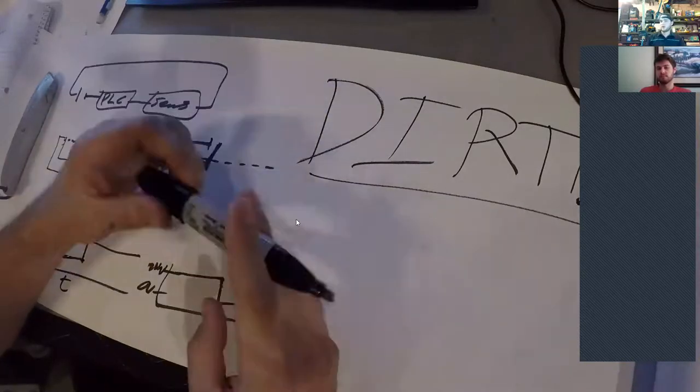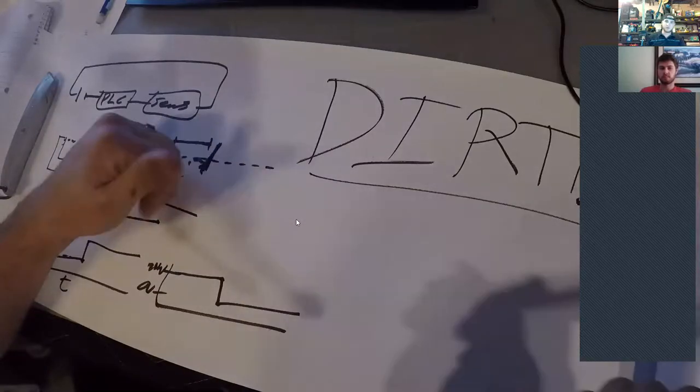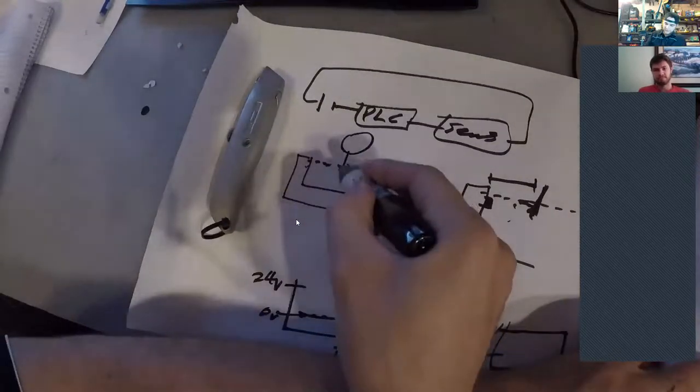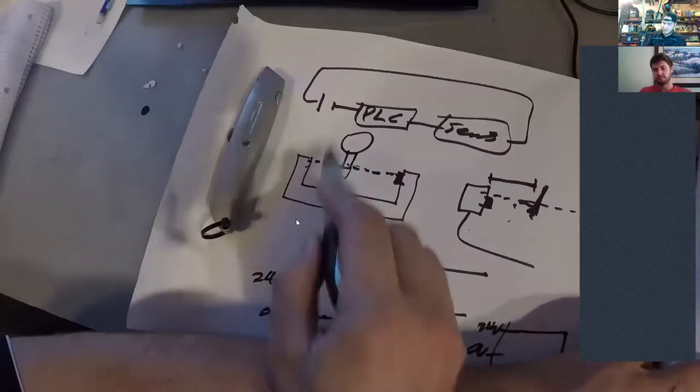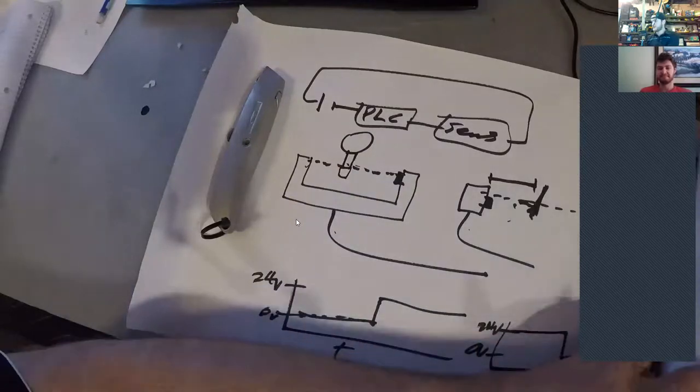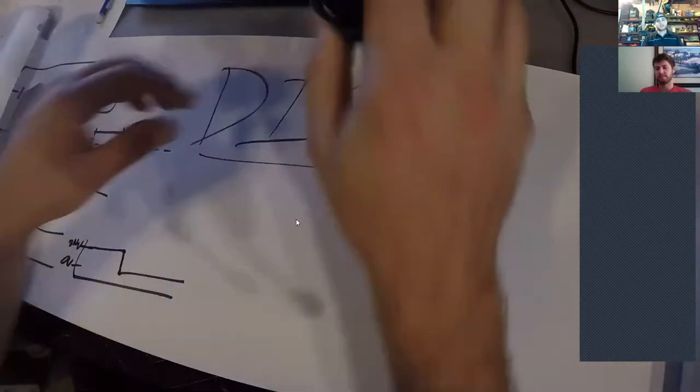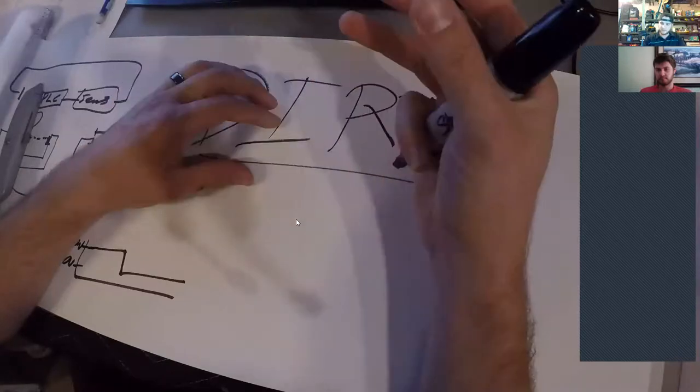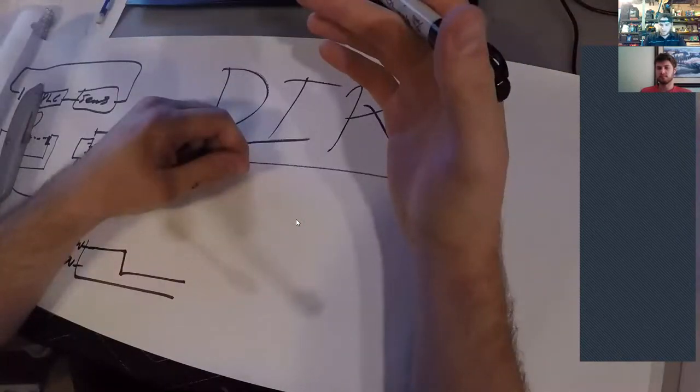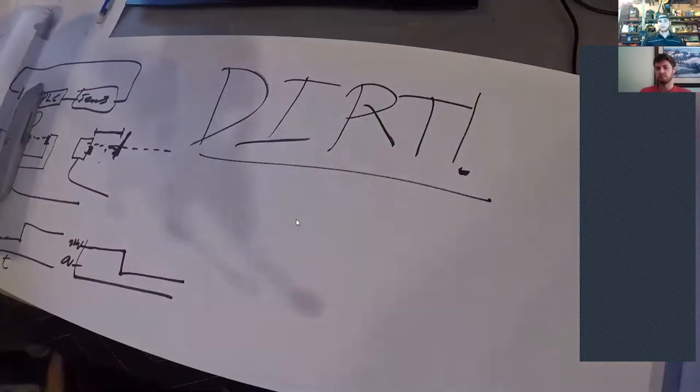Dirt and dust is a problem. So in an industrial setting, you can just get dirt or crud on your sensor and it'll block the light and it won't work correctly anymore. So we actually had that happen on a conveyor system where we were basically built our own encoder similar to what we did with that motor.